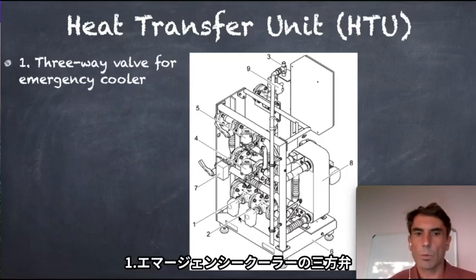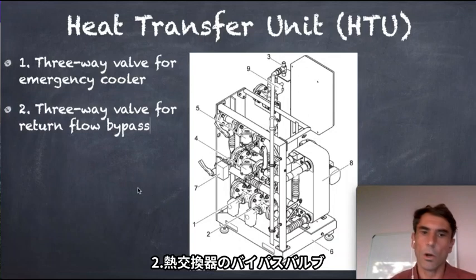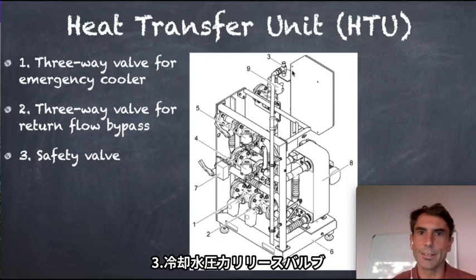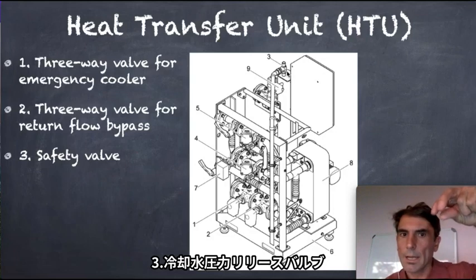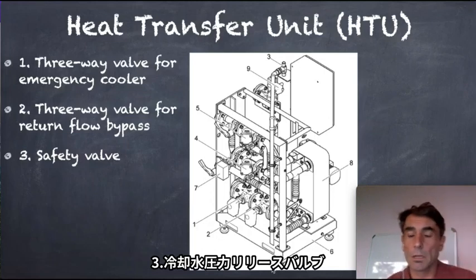Then from the other side, we have here number 1, the three-way valve for the emergency cooler. Number 2, we have the bypass valve of the plate heat exchanger. Number 3, where's number 3? Here on top, the safety valve again. This is the overpressure safety valve, again with the red cap, and this releases pressure. If you get overpressure over the limit, there's a spring valve that will release through that pipe and release it here to the floor.